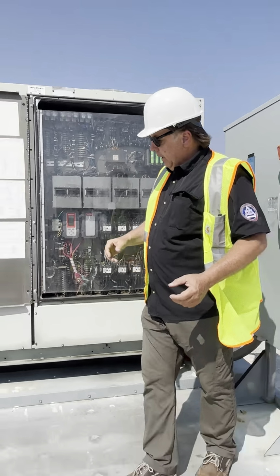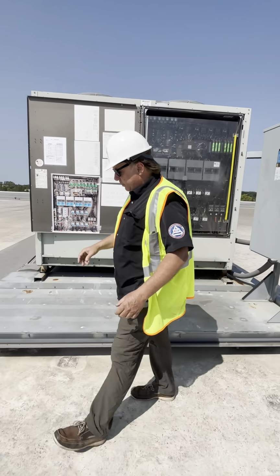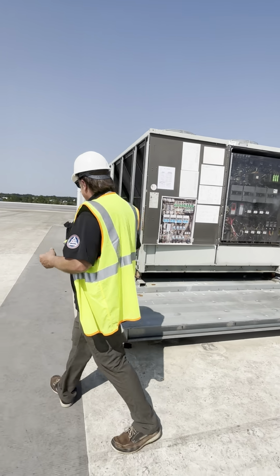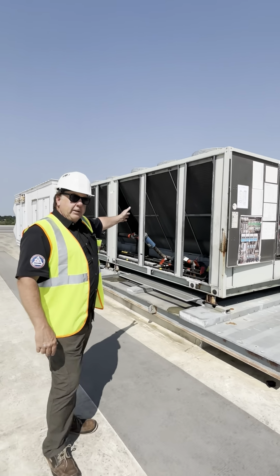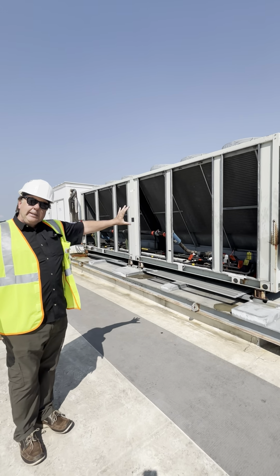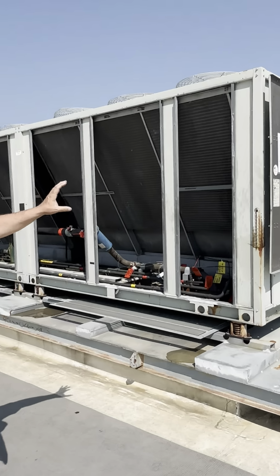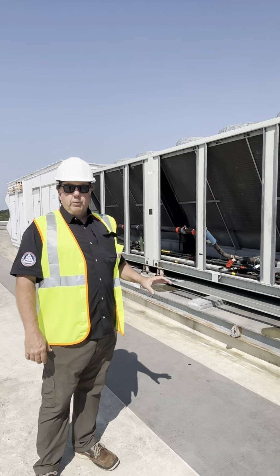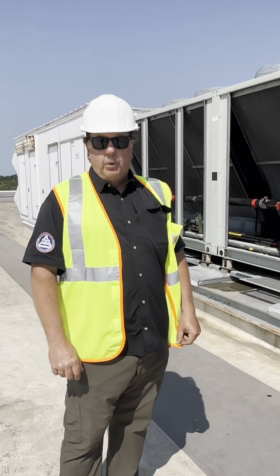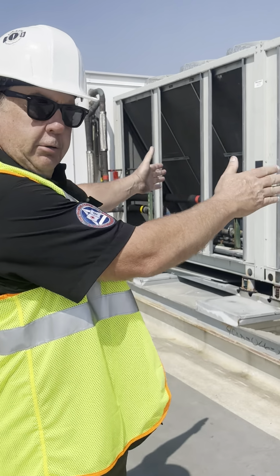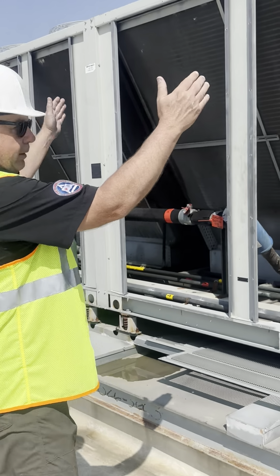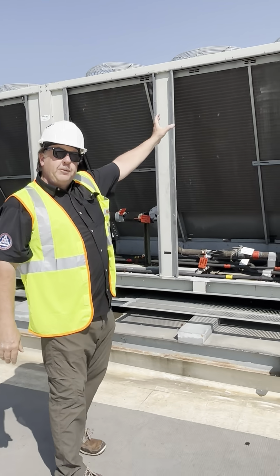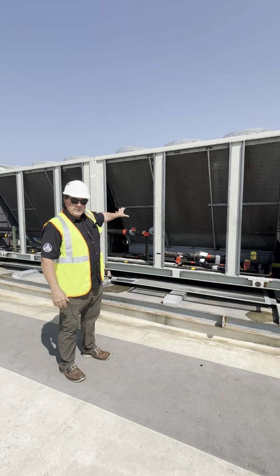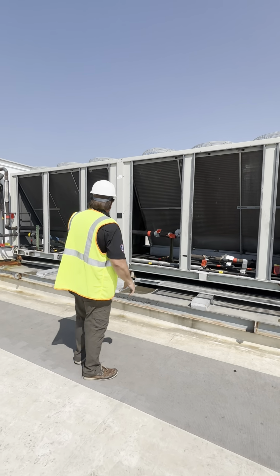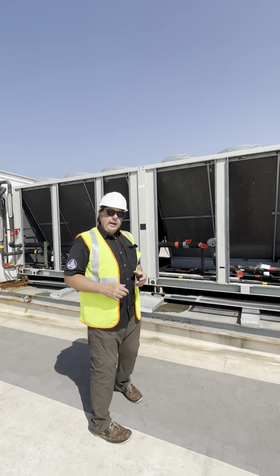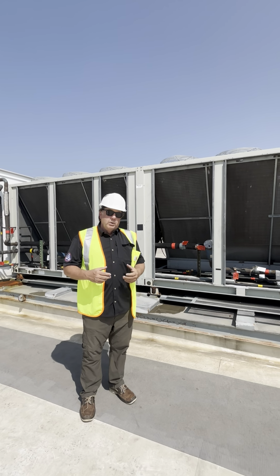Things like that. As we go around the side over here, we can see the condensing unit. So right here, this first half is the condensing unit. Well, this is a 100-ton condenser that originally was R22 being converted to 407. You're looking at two circuits. You've got the circuit here, which has 6 fan motors on the top, and then we'll see on the other side 4 compressors. You've got the circuit over there, which also has 6 fan motors and 4 compressors.